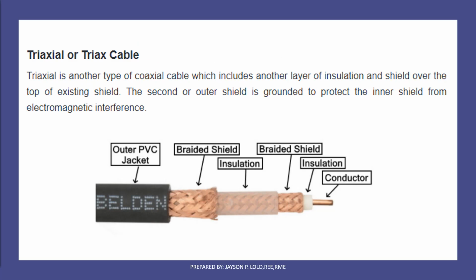Third one is the triaxial or triax cable. It has 6 parts: outer PVC jacket, braided shield, insulation, braided shield, insulation, and the conductor. This is a highly protected cable to avoid electromagnetic interference or signal interference.